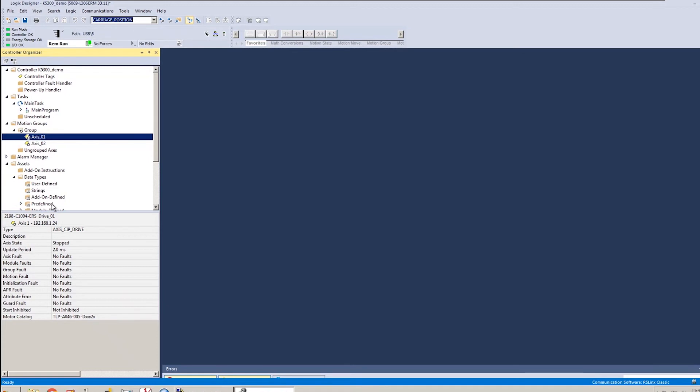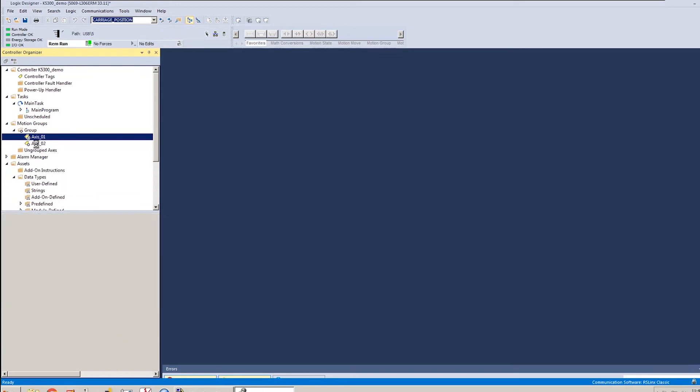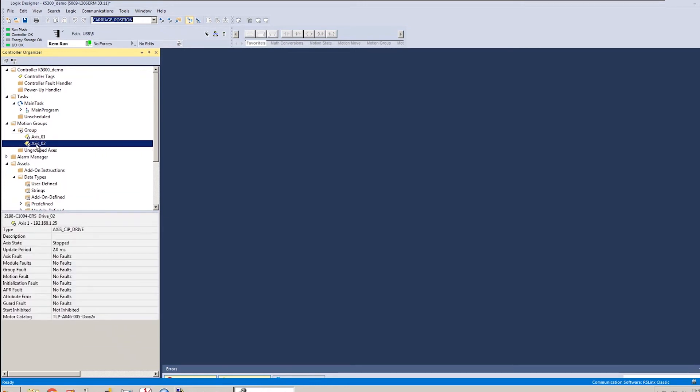And whatever you click on in your controller organizer, it will show status about that here. So axis one, it tells me I'm in the stop state. That's good. That's where I want to be. That means that the download happened correctly. I've got the voltage I need in order to run. I just haven't enabled or been given a command yet for that axis. Same thing here with axis two. We're in the stop state. That's good. That's where we want to be.